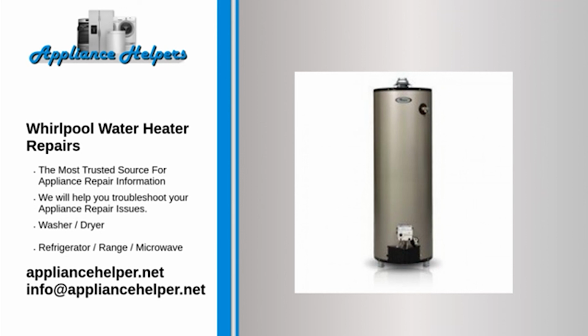most homes now need a thermal expansion tank and a properly adjusted pressure regulating valve. Not having a thermal expansion tank is the most common reason for a dripping discharge pipe.